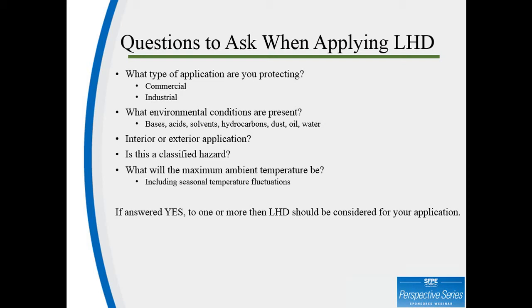As John touched on earlier, the jacket is the detector's protection from the local environment, so it must be chosen carefully. Moving on, is your application within a classified area? Digital linear heat detection can be made intrinsically safe through the use of ISBs or intrinsic safety barriers. Keep in mind, this is very different from explosion-proof detectors. There is no explosion-proof Protectowire. Rather, the use of intrinsic safety barriers enables the standard detector to be located within a classified area. With this type of application, the properly rated control equipment and relevant FM-approved control drawings must be followed and used.